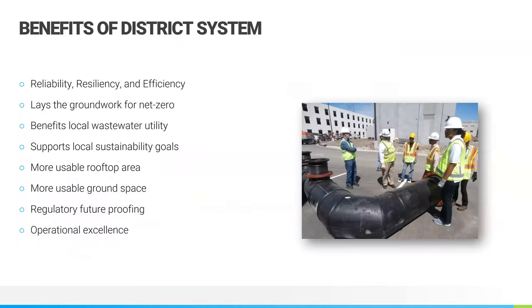Wow. So what are you getting out of that district system? You're getting a lot of reliability. It's been proven that district energy systems provide a much more reliable source of heating, cooling and hot water to their buildings. You see them all over Phoenix. Here in Denver, there's a downtown district loop. A lot of downtowns already have these district loops in place. They just haven't been this ambient single pipe style. But the reliability, resiliency and efficiency of them has been proven year over year.